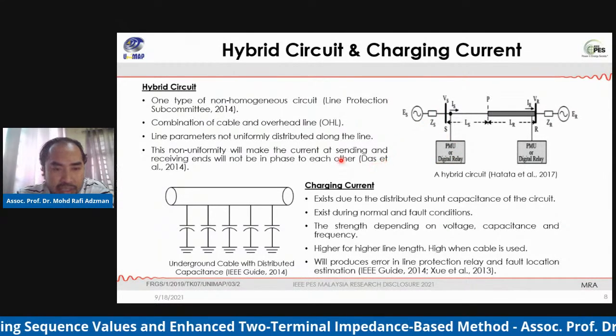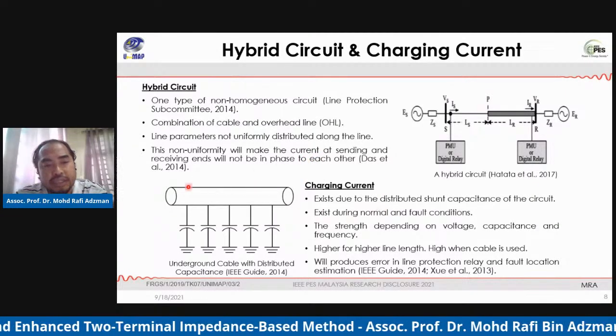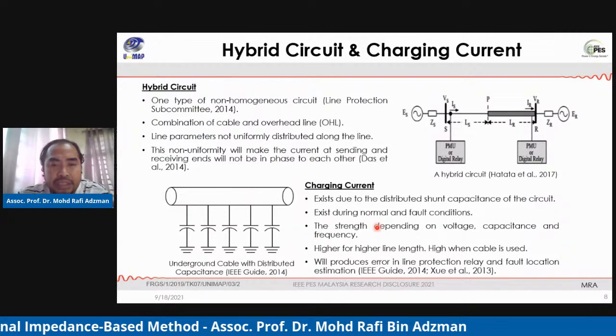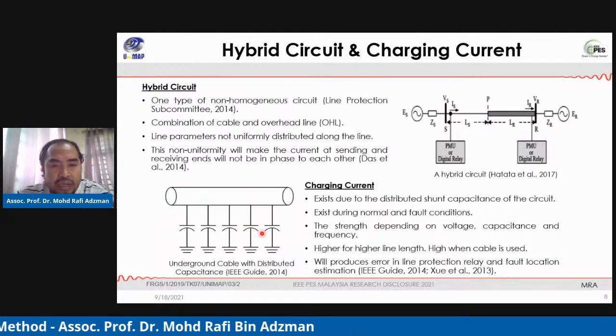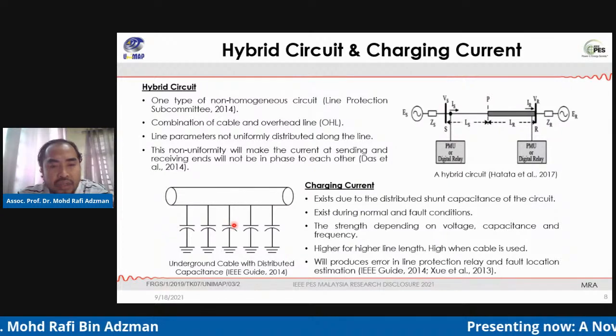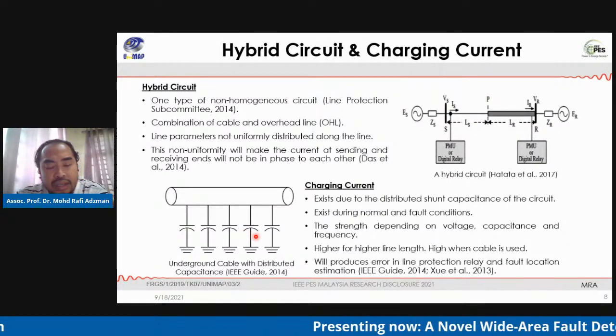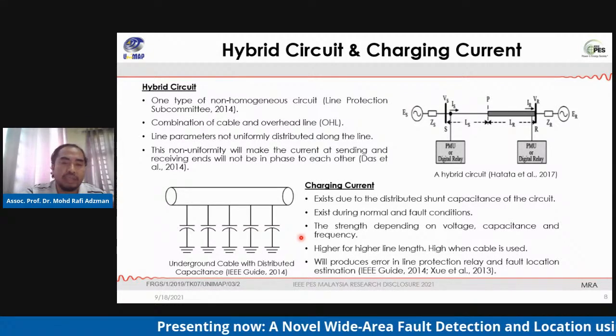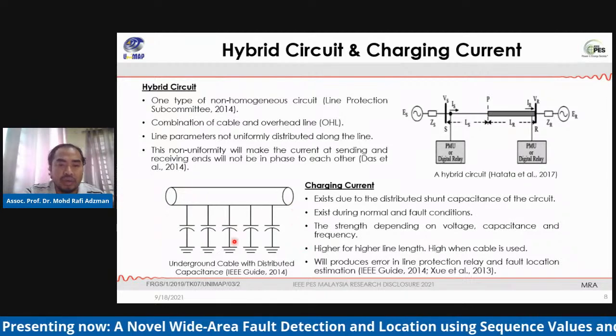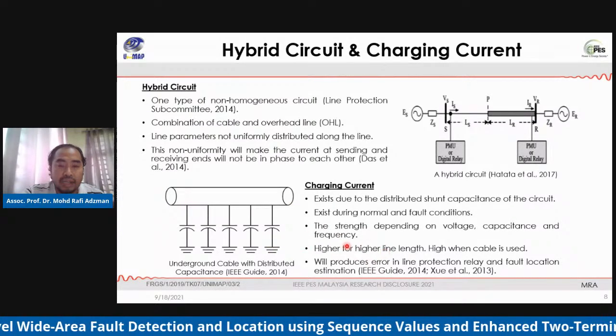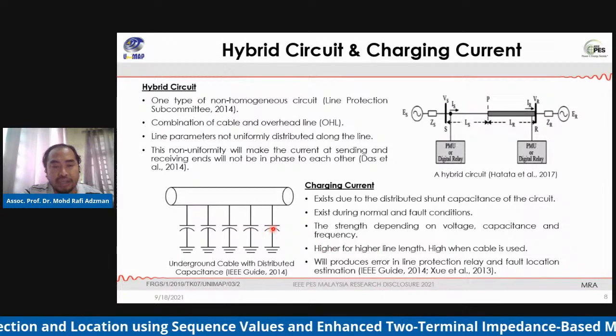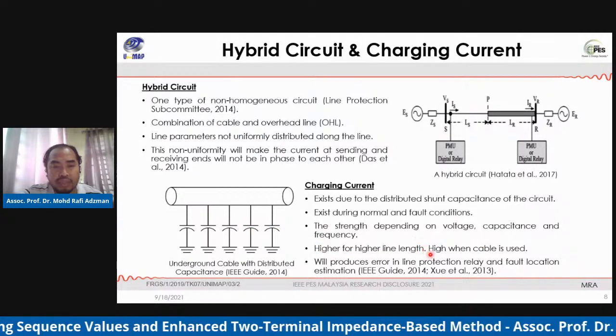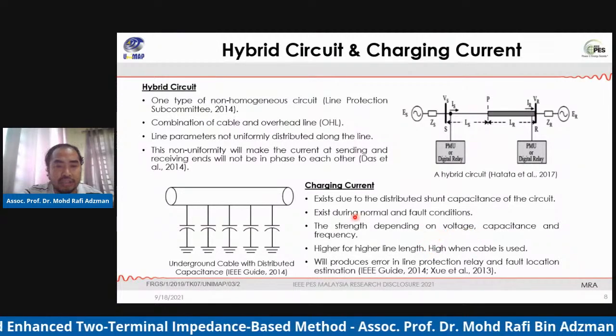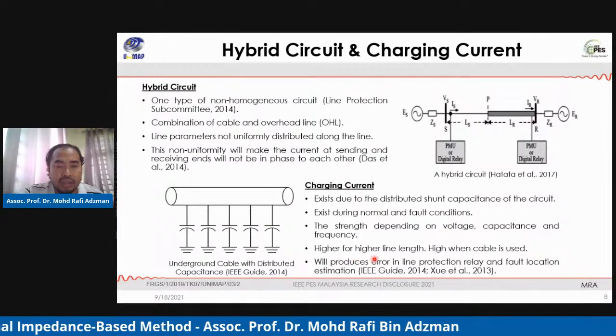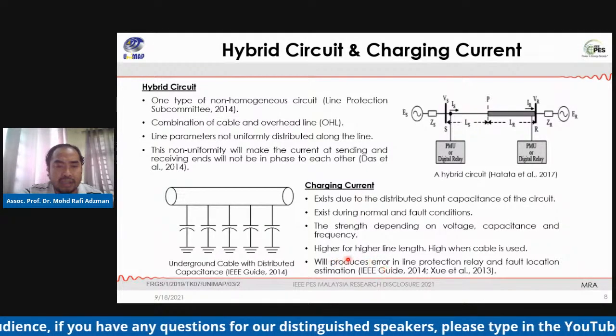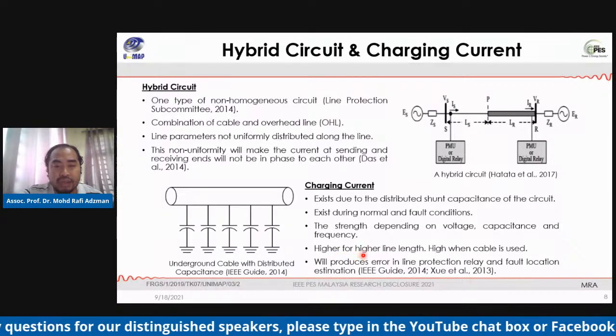Another issue is regarding the charging currents. The charging current exists due to the distributed shunt capacitance of the circuit, so it exists during normal and also fault conditions. The charging current strength depends on the voltage, the capacitance, and the frequency. For long line lengths, the charging current will be much higher compared to short ones, and when we use cable, it will give more charging current. According to the IEEE guides, it will produce error in the line protection relay and fault location estimation.